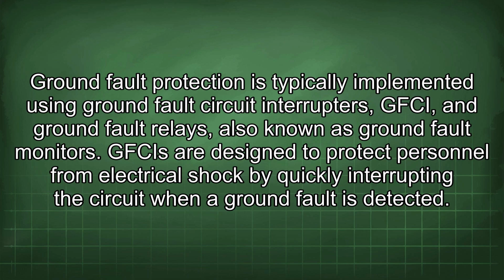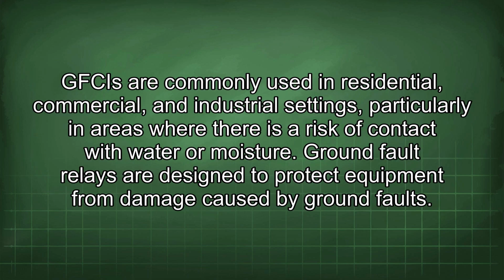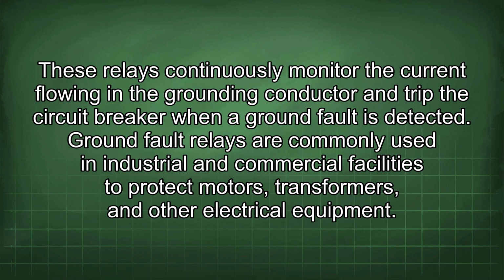GFCIs are designed to protect personnel from electrical shock by quickly interrupting the circuit when a ground fault is detected. GFCIs are commonly used in residential, commercial, and industrial settings, particularly in areas where there is a risk of contact with water or moisture. Ground fault relays are designed to protect equipment from damage caused by ground faults. These relays continuously monitor the current flowing in the grounding conductor and trip the circuit breaker when a ground fault is detected.